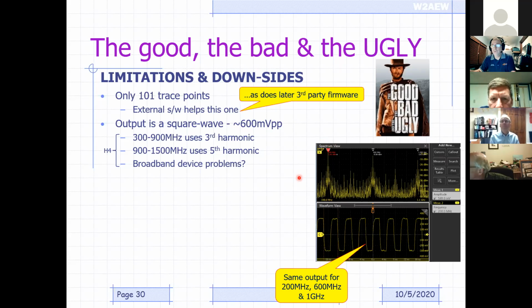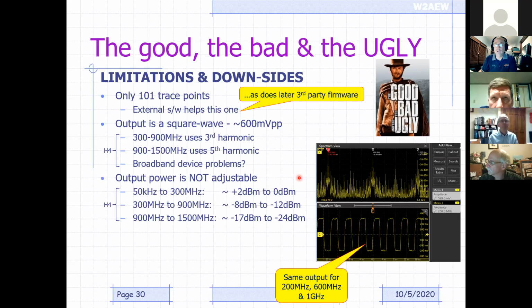So if you're measuring an amplifier or a filter, you have to remember that the device is getting hit by this square wave. So it's going to be seeing the fundamental, third, fifth, and even higher order harmonics. You also have to remember that the output power is not adjustable. In the case of the H4, from 50 kHz to 300 meg, the fundamental of that square wave is about 0 dBm, 0 to about plus 2 dBm. You can't adjust it up or down unless you throw an attenuator there. The third harmonic is about 10 to 12 dB lower than that.